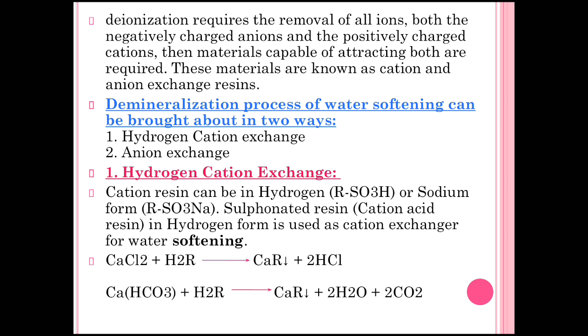Deionization requires the removal of all ions — both the negatively charged anions and the positively charged cations — so materials capable of attracting both are required. These materials are also known as the cation and anion exchange resins. These resins generally have a structure like molecular sieves, which are very small and white, and have the capacity of exchanging cations and anions. The impurities present in water get captured by these molecular sieves, and an equivalent amount of ions are released by the cation and anion exchange resins respectively.